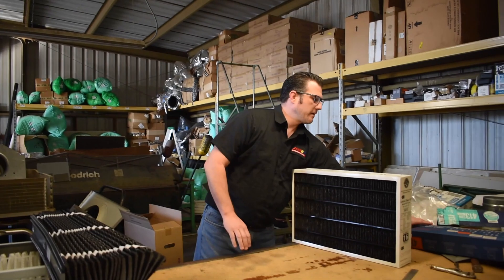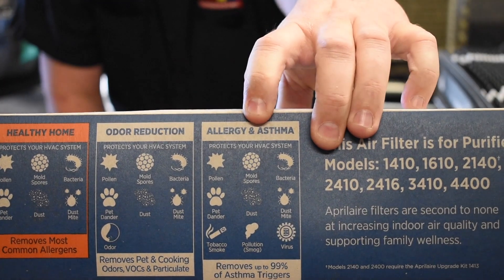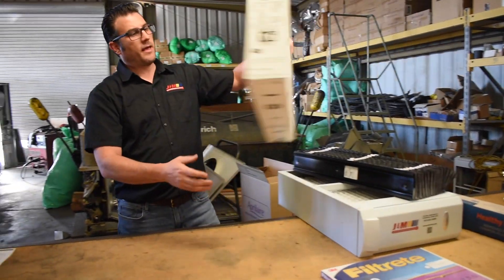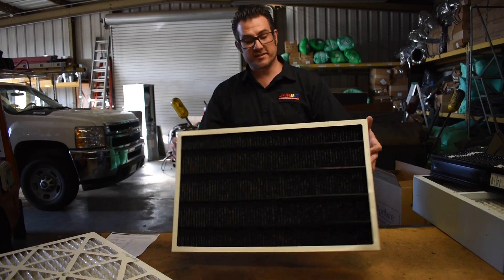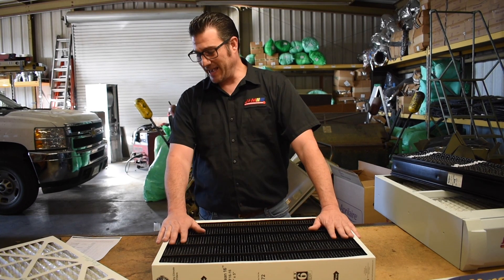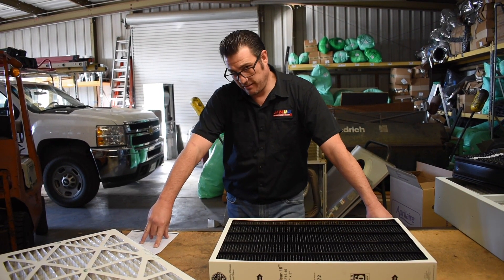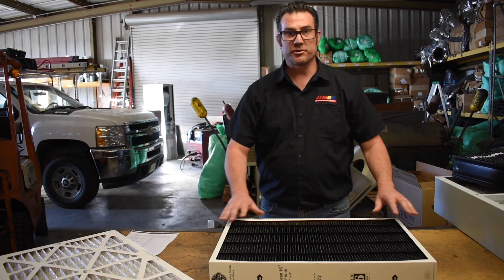Aprilaire also makes a very high allergen and asthma filter, and they have four different filter options for this cabinet. Now Healthy Climate has a MERV-16 filter, and this MERV-16 is also a carbon filter, so it's going to handle odors as well. But it's going to collect even smaller particles — a MERV-16 is rated at greater than 95% of particles between 0.3 and 1 micron. That's really small; viruses and things like that are going to get captured in this filter.